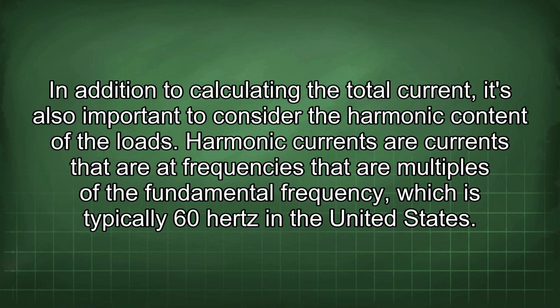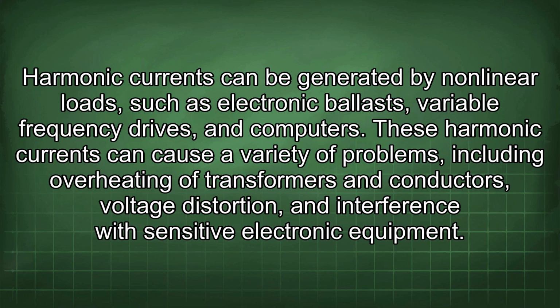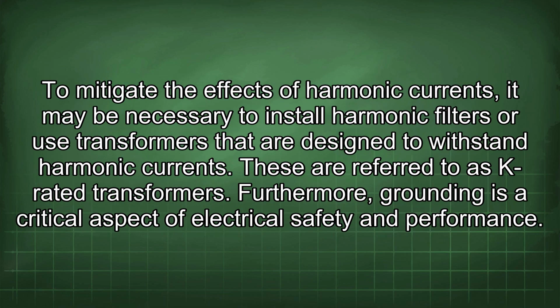In addition to calculating the total current, it's also important to consider the harmonic content of the loads. Harmonic currents are currents that are at frequencies that are multiples of the fundamental frequency, which is typically 60 Hz in the United States. Harmonic currents can be generated by nonlinear loads, such as electronic ballasts, variable frequency drives, and computers. These harmonic currents can cause a variety of problems, including overheating of transformers and conductors, voltage distortion, and interference with sensitive electronic equipment. To mitigate the effects of harmonic currents, it may be necessary to install harmonic filters or use transformers that are designed to withstand harmonic currents. These are referred to as K-rated transformers.